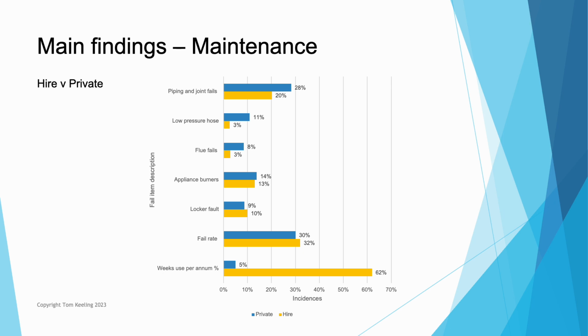This slide shows some differences between hire and private boats. We can see there's definitely a greater number of piping and jointing faults in the private sector, much more incidence of hose failure, much more incidence regarding flue fail points. Appliance burner faults are equally reported, suggesting that higher usage in hire is affecting operation of appliances. Locker faults were found to be the same as well.